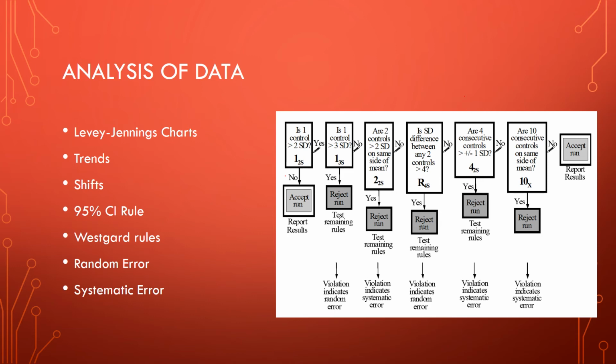Potentially, one of the other things that could happen is you did have a lot change in the control, but you never changed the lot inside the instrument. That's one of the things that these newer instruments require, that you update the lots within the instrument, and if you don't do that, you'll probably see a shift in the results that you get.